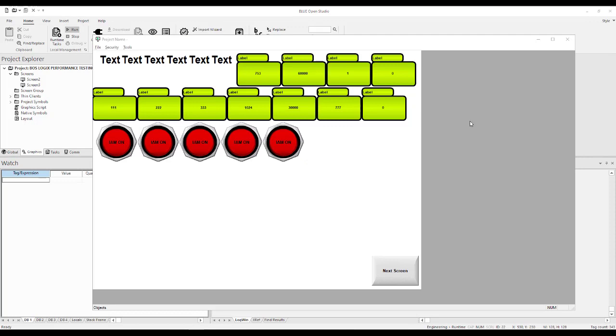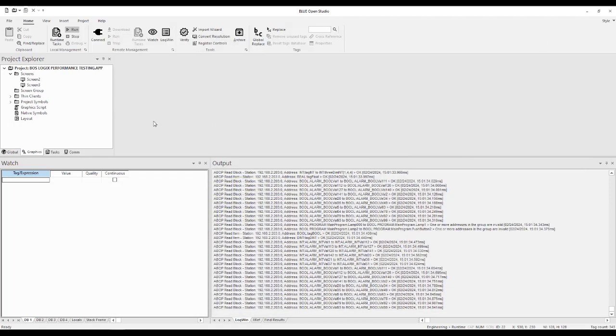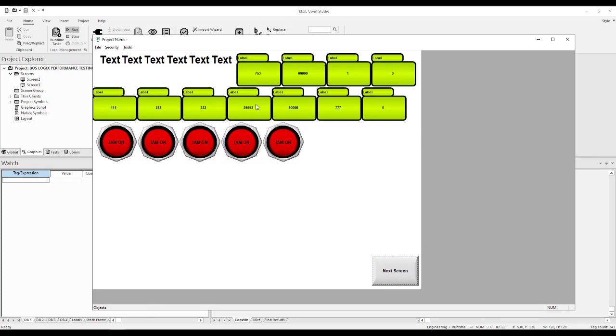So about this subject regarding what is the best way to use this Rockwell CIP driver when we're talking to one of these Logix platforms, I'm actually going to reserve judgment on that. You will notice that I am in the midst of creating a performance testing application, so I'm going to continue to add tags to this tag integration, and then in the end see how it's actually performing. One of the things you can look at here is that I've got this 1 millisecond timer running, and I'm getting 1 to 2 second updates just in that.